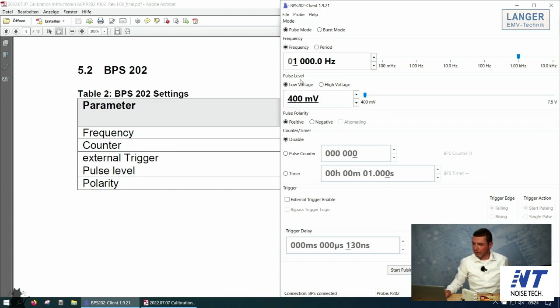Then the next is the pulse level. Here we have two ranges: a low voltage range and a high voltage range. For the calibration, of course, you have to test both ranges. We start now with the low voltage range. This low voltage range starts at 400 millivolts and goes up to 7.5 volts. In the high voltage range, it takes some time to change it. Here we start from 8 volts to the maximum level of 40 volts.